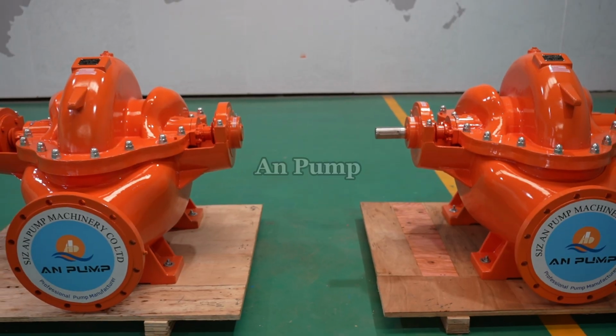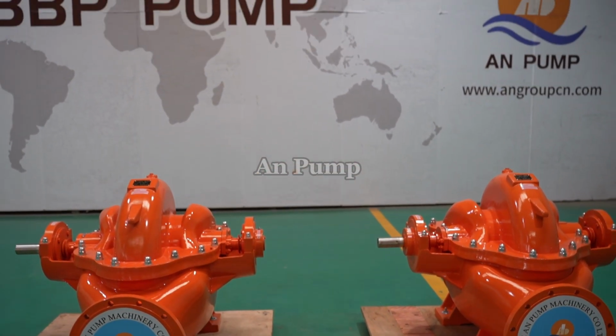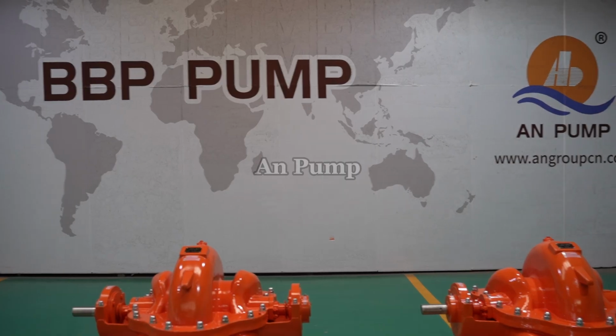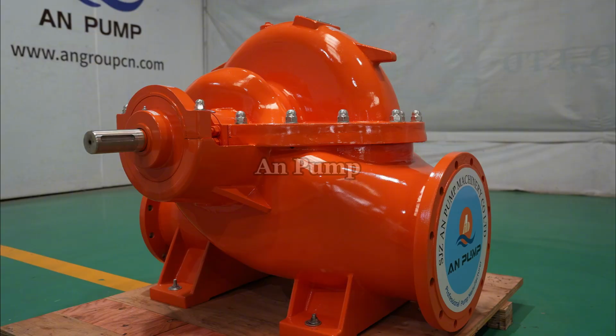Split case pumps are used in municipal water distribution, large fire suppression systems, big HVAC systems, power plant cooling circuits, and flood control. They can handle enormous flow rates, from 200 gallons per minute all the way up to over 100,000 gallons per minute. Heads go up to about 600 feet per stage. The downside is size and cost. These pumps are physically large and much more expensive than end suction pumps with the same flow capacity. They also need more floor space and careful alignment.